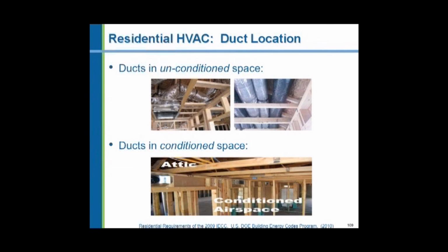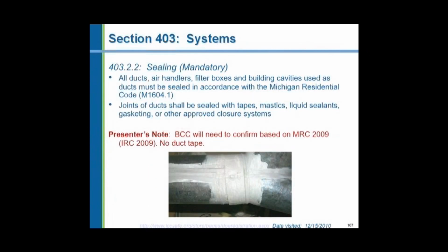Think for a moment about a building where you've constructed an R20 wall and an R38 insulated ceiling, and 7 times every hour you take the entire volume of air in that space and you run it up through an R8 or an R6 insulated duct in the attic. That totally defeats all of the effort and money you've put into insulating the rest of the building. So I, as a professional engineer, would recommend installing the ceiling insulation over the top of this ductwork in the attic. We must now seal ductwork where we never had to before.